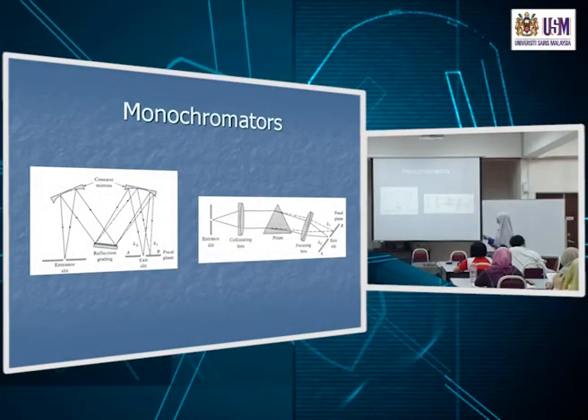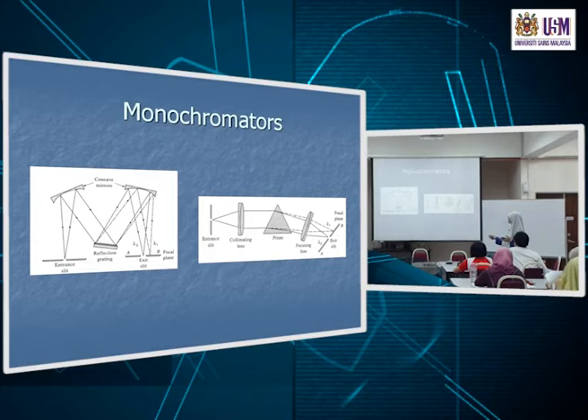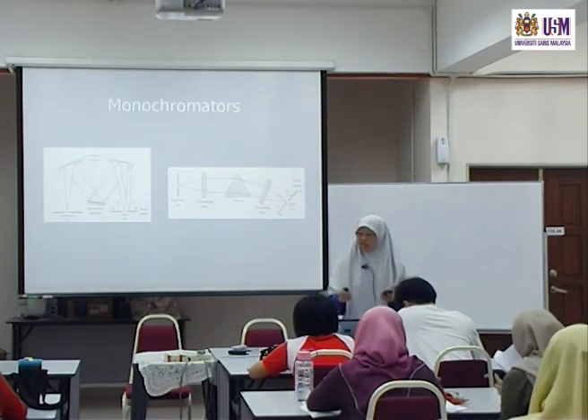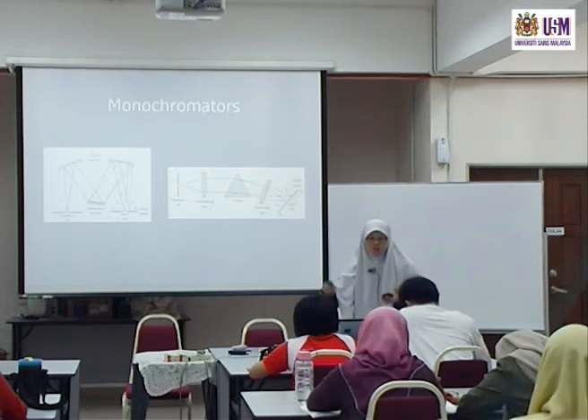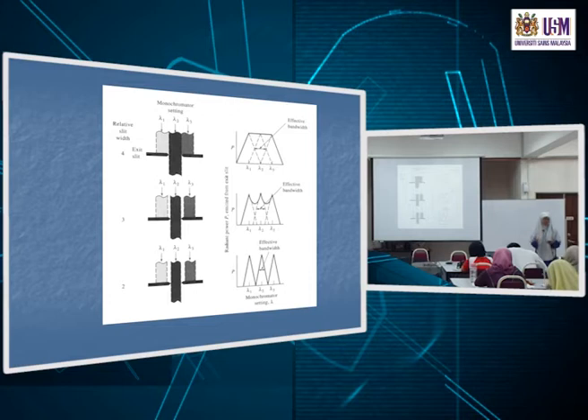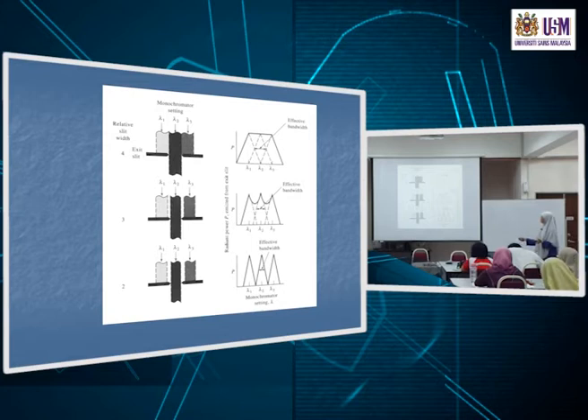With the narrowest slit width, we look at the light coming out as we continuously change the setting from λ1 to λ2 to λ3. What component do we change to decide which wavelength comes out of the exit slit? We have two kinds of monochromators — one using a prism and one using a grating. We change the position of the grating or prism to select λ1, λ2, or λ3.